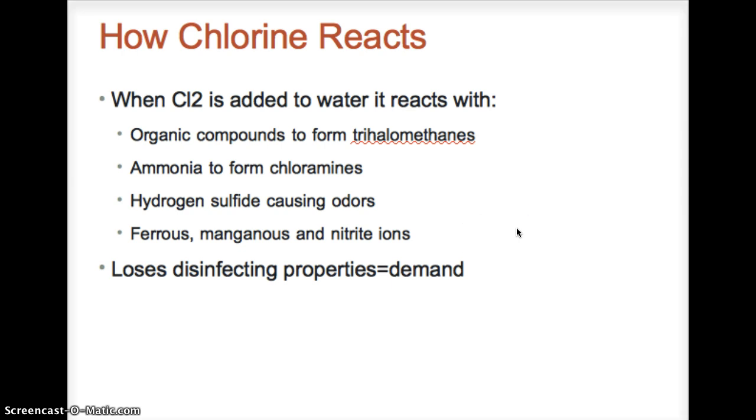It also reacts with hydrogen sulfide, which can cause odors, and it reacts with the ferrous, manganese, and nitrite ions. And what is known as demand is the fact that the chlorine that is added is losing its disinfecting properties. And as we look at the breakpoint curve, you will see a little bit more of what that means. We're going to review that in just a second.